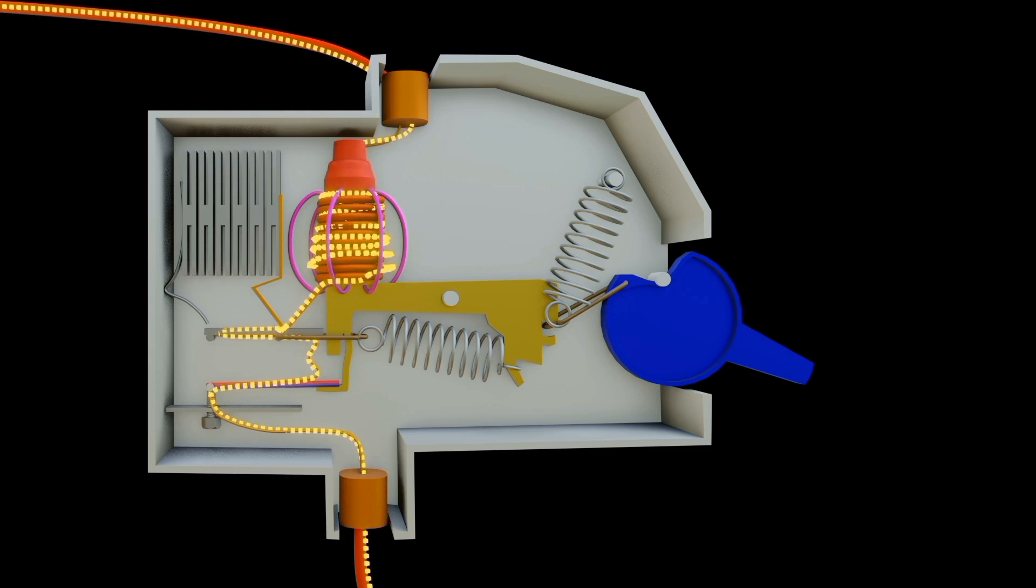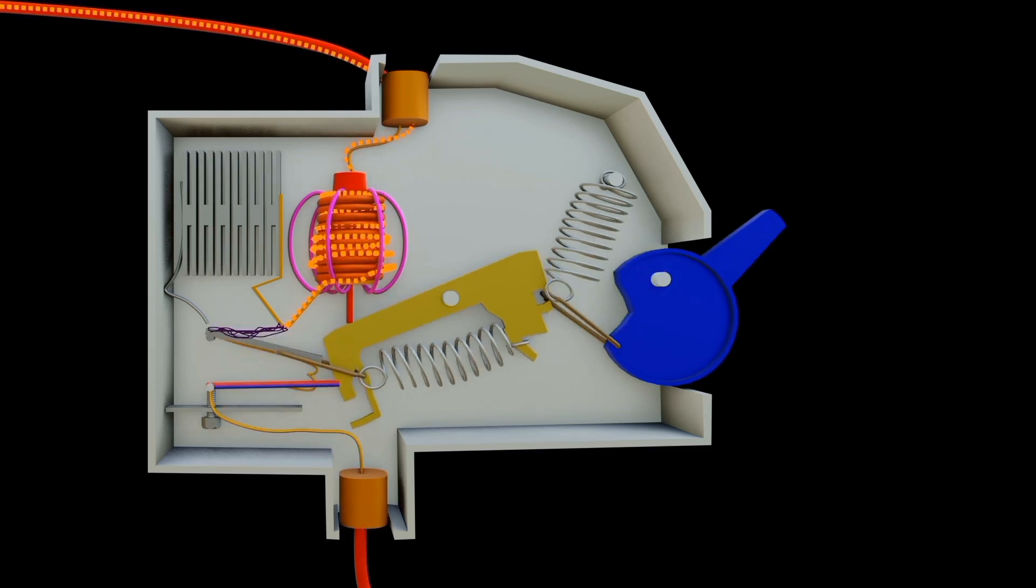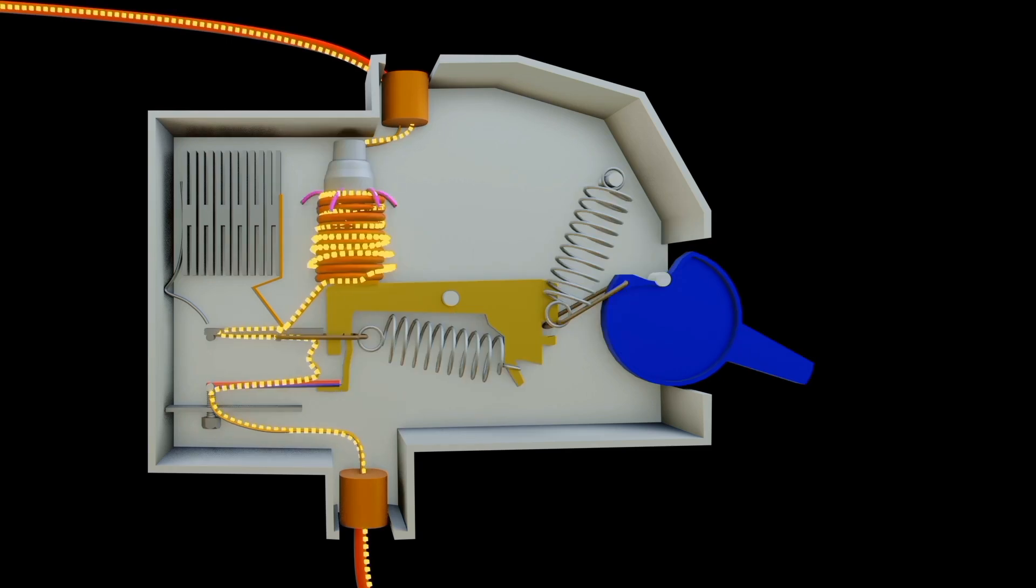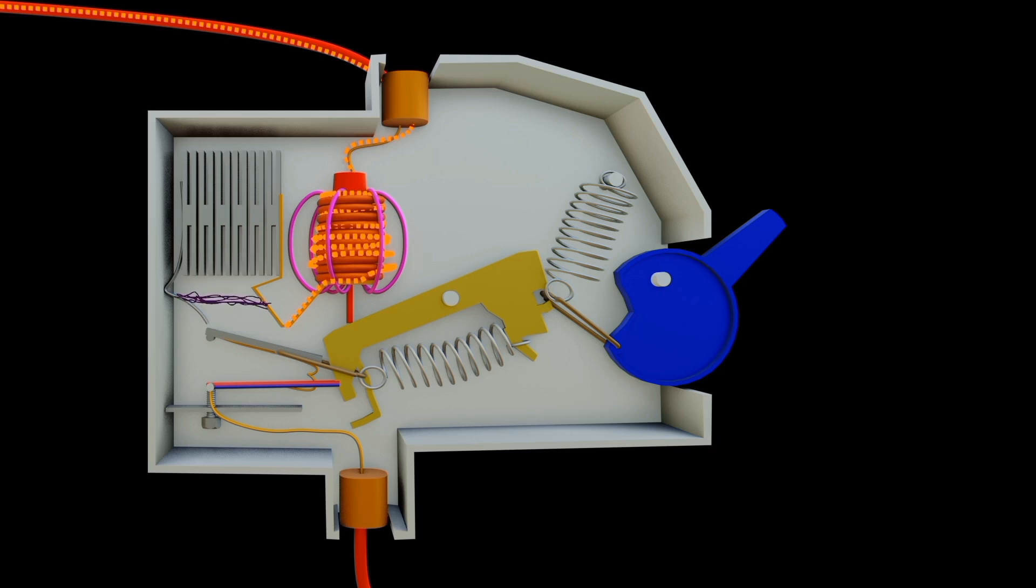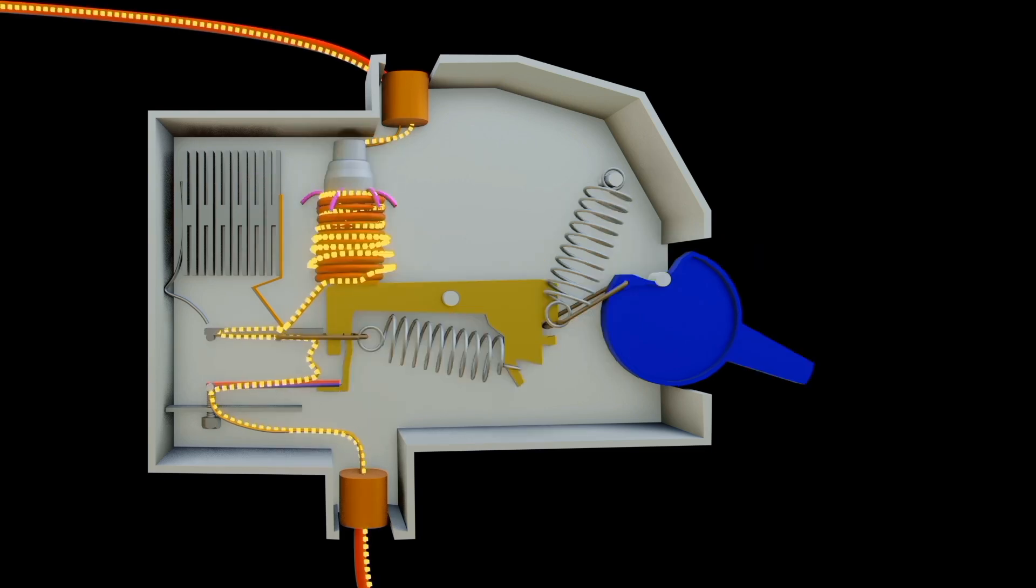Certain materials within the arc chamber are chosen for their ability to deionize the surrounding air. Deionization helps in reducing the conductivity of the arc, making it easier to extinguish. Metallic plates and grids contain materials like copper or tungsten. They have good thermal conductivity and can withstand the high temperature generated by the arc. Also ceramics or composite materials may be used since they have ability to withstand high temperature and insulating capacity.